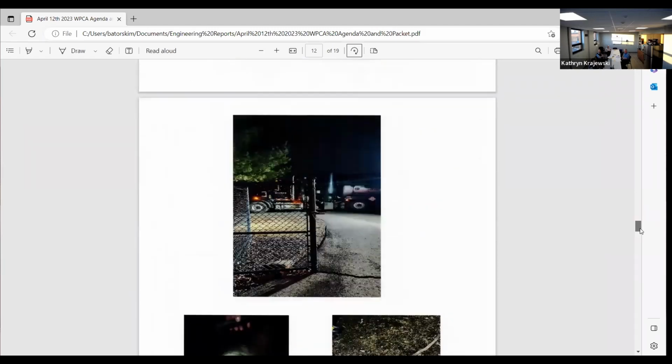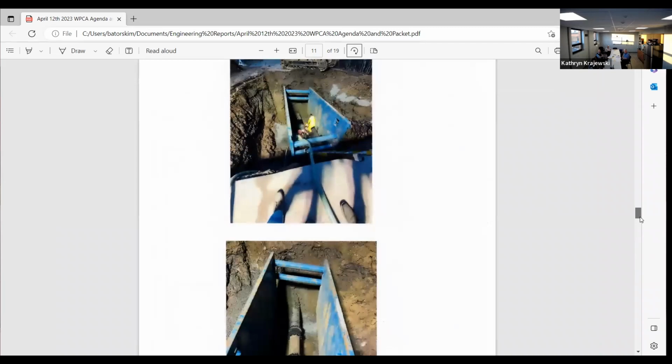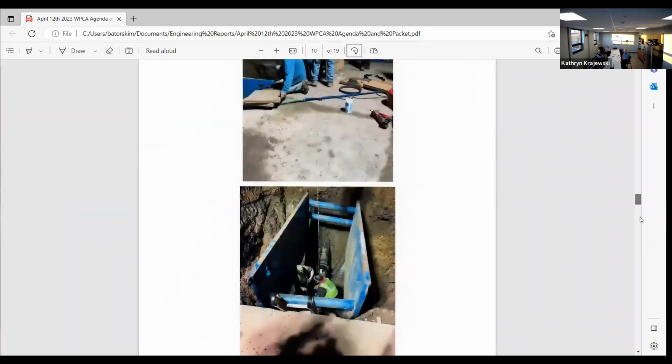We had McVac trucking everything from the wet well that we could get up to the jug handle and dumping it. We tried to keep up with as much as we could, and we were on about, like I said, 12 hours after it originally broke. This was the section we put in. It was about an 8-foot section. This was them cutting the old one out. And this was them basically lowering the new section in.